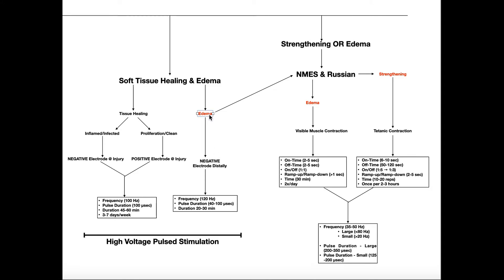If you're going to choose to treat edema with high-voltage pulse current, the negative electrode is actually going to go on the site of the edema or distal to that. The positive electrode is going to be proximal, and that will allow that fluid to move distally to proximally — to move it back to the heart. High-voltage pulse current for edema has these parameters: a frequency of 120 hertz, a pulse duration of 40 to 100 microseconds, and the duration is going to be 20 to 30 minutes. Refer back to the video on high-voltage pulsed current for these ranges.